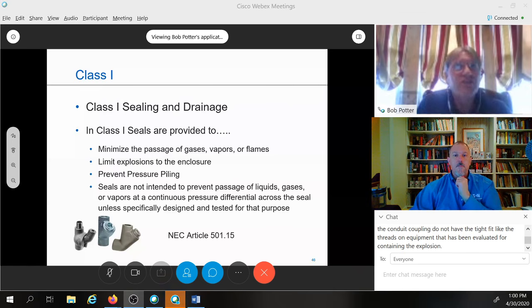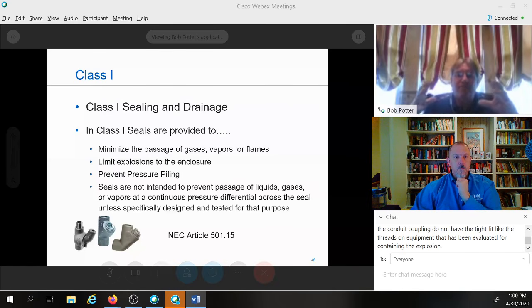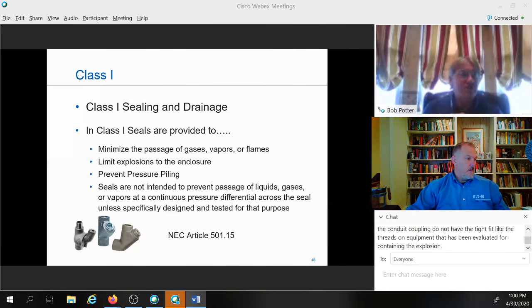And so I've actually seen projects where transportation companies have buses that operate on both gasoline and diesel, and the local authority having jurisdiction for those repair areas has required the ones for gasoline to follow Chapter 5, Article 500 and 501 of the National Electrical Code. But for those areas that can accept the diesel buses, they've allowed them to remain non-classified, providing that they make sure that only a diesel bus would ever go in that particular repair garage, and a gasoline bus would never go in it.